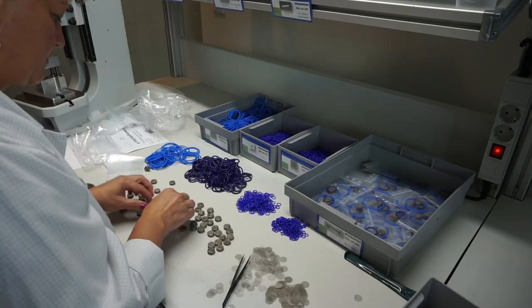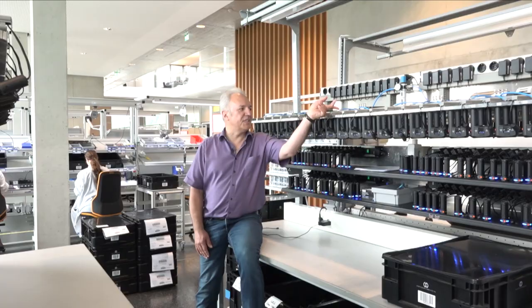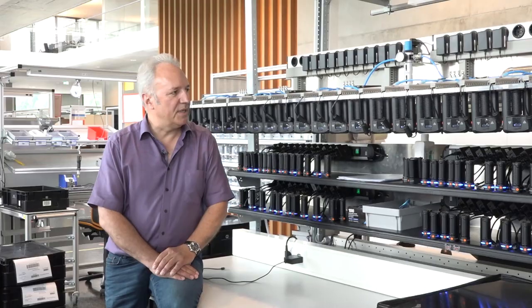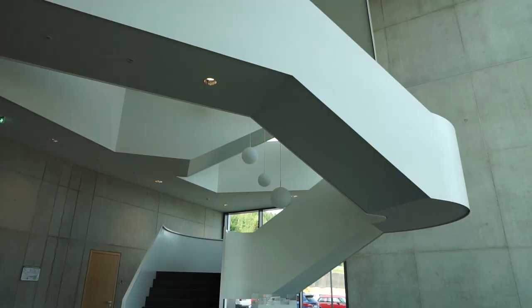After the Mighty and Crafty have been assembled, the batteries have to be charged so that we are able to test the devices. We charge the batteries and then perform a suction test — what you see here is a suction tube. After the batteries are charged, we draw air through the device to see whether it works correctly. Every single product is tested.